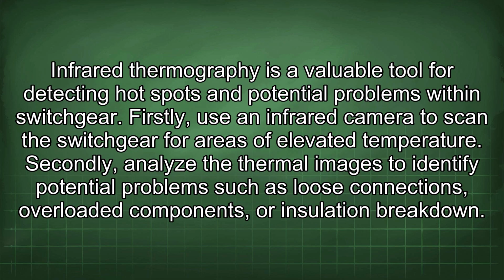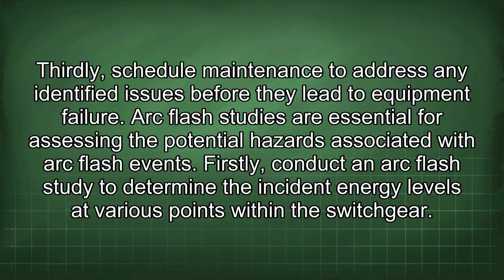Infrared thermography is a valuable tool for detecting hot spots and potential problems within switchgear. Firstly, use an infrared camera to scan the switchgear for areas of elevated temperature. Secondly, analyze the thermal images to identify potential problems such as loose connections, overloaded components, or insulation breakdown. Thirdly, schedule maintenance to address any identified issues before they lead to equipment failure.